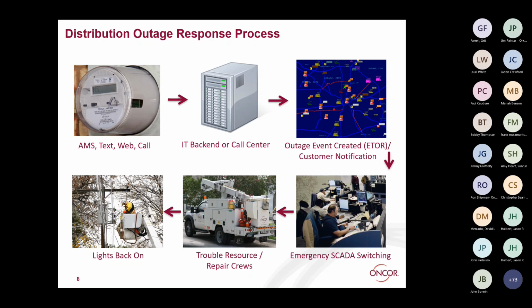Then you have that automatic roll-up, where these outage calls get bundled up to the device level with the predictive state - it's this transformer, this fuse, whatever is the source for that outage. That's what the operator is looking at. At that point we're generating an automated estimated time of restoration. The customer gets notified that an outage was reported affecting their home, here's the estimated time of restoration, and we'll keep them updated on the progress.